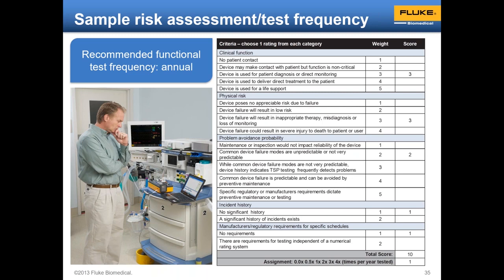And again, I'm not going to go into this in great detail here, other than to show you the total risk score that is obtained using this worksheet is 10. Any test that is 13 or higher would be twice per year. Well, this is not even 13, it's only 10. So an overall risk score between 9 and 12 would be tested once per year. And so we are 10, therefore that's the applicable one. So the testing that we would do, how often we would test patient monitors, should be once per year. Now, keep in mind, this is how often we're going to do our scheduled testing.